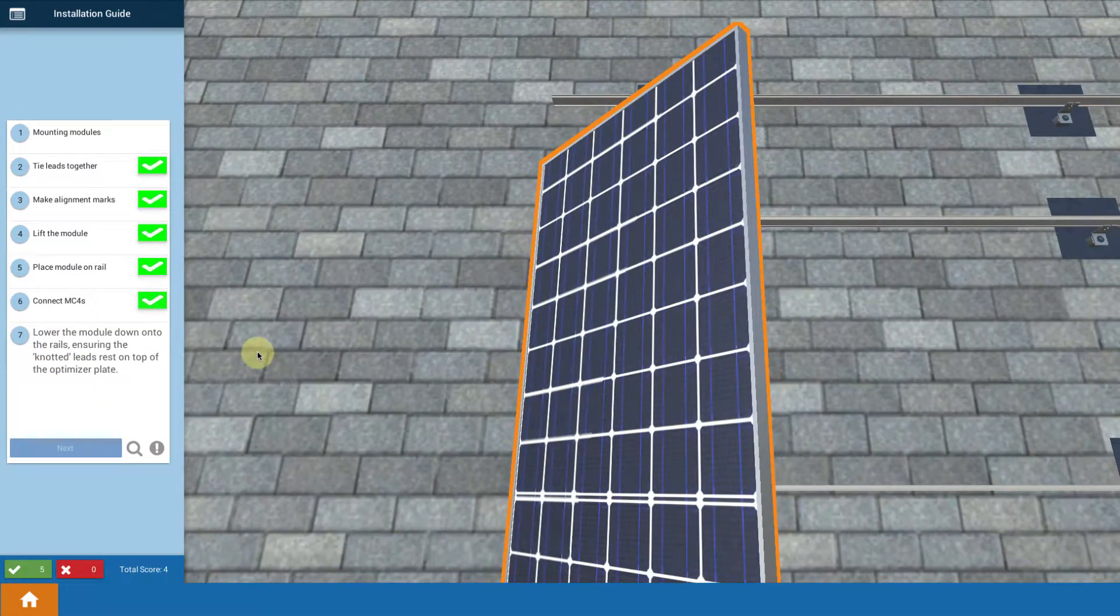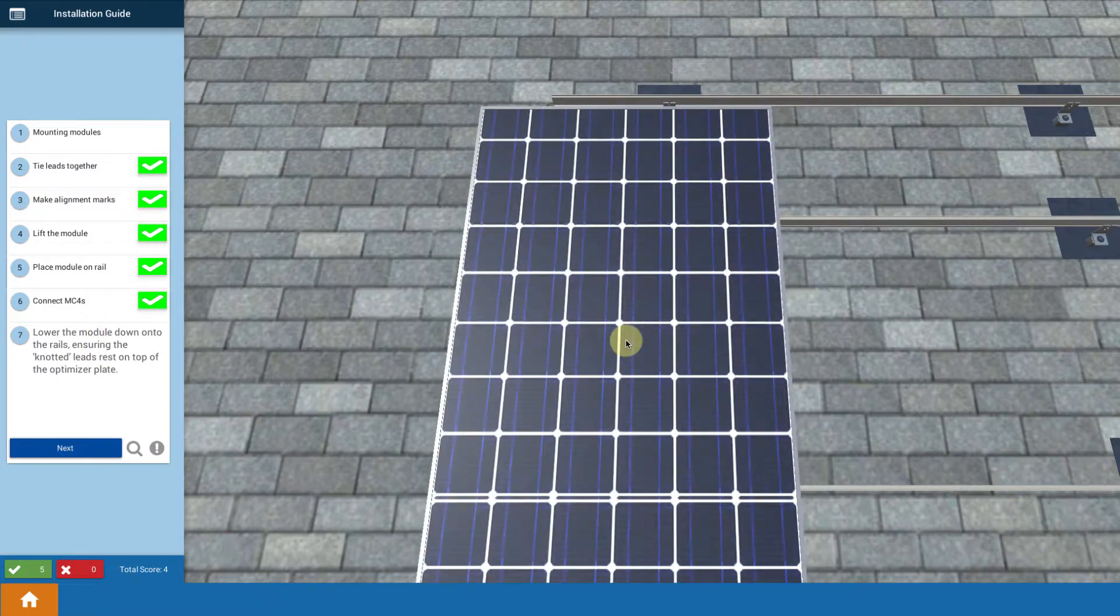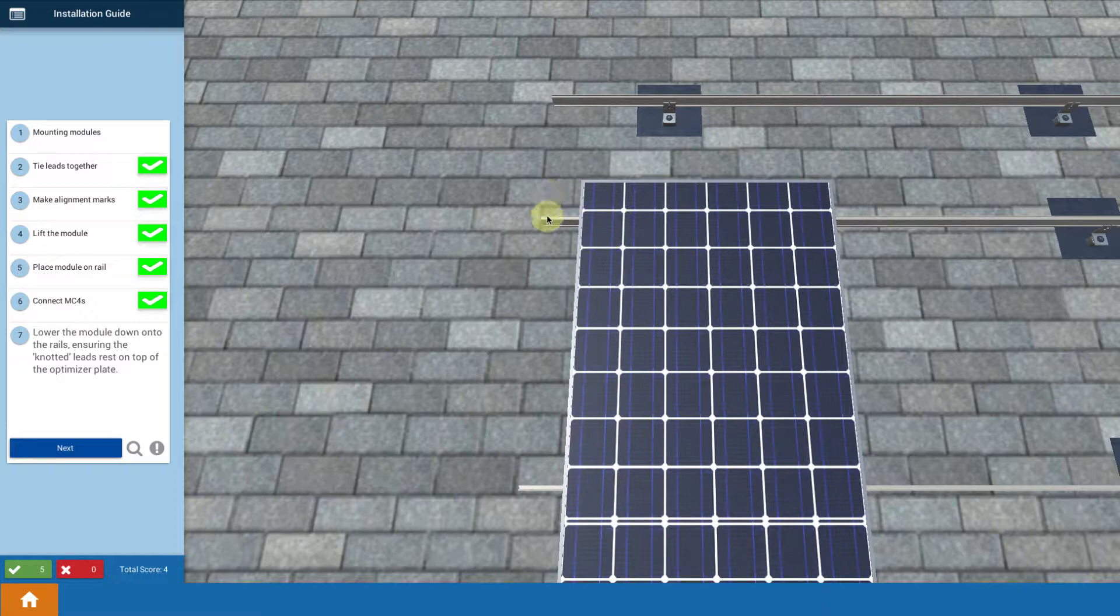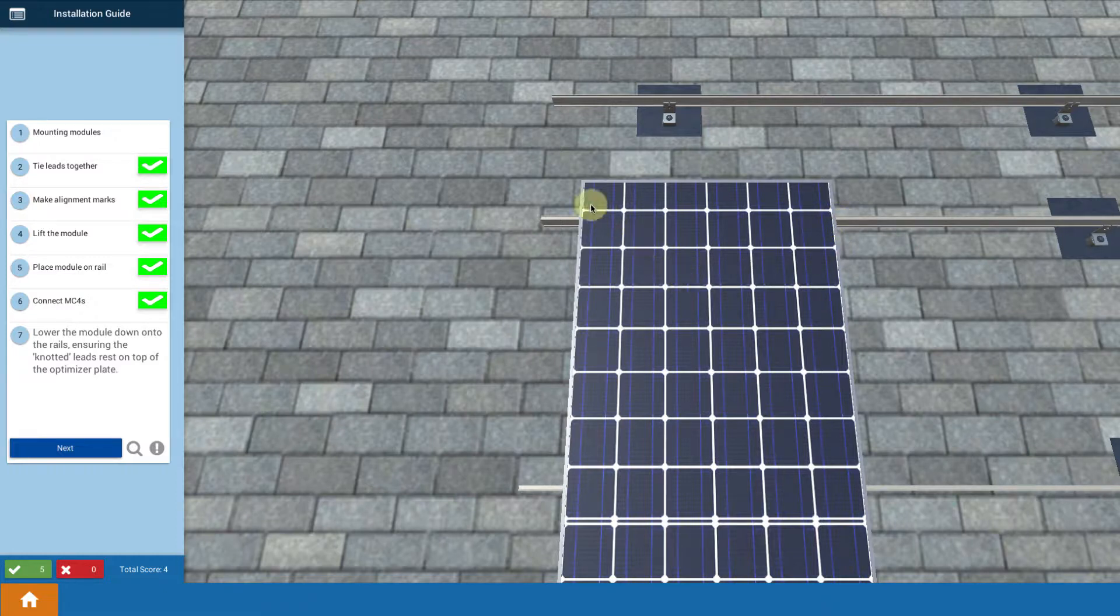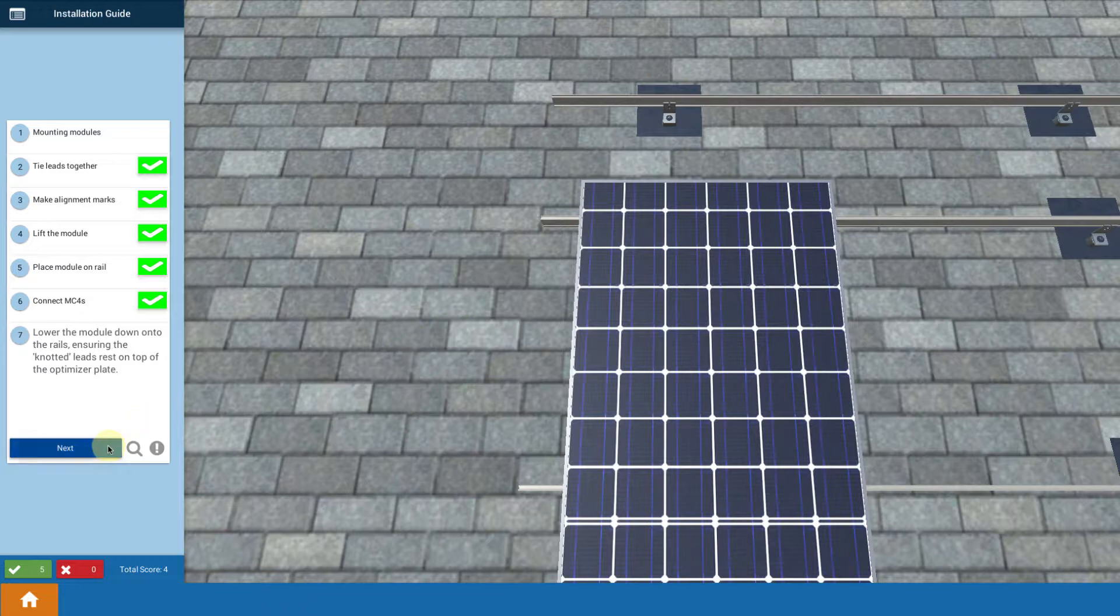Now this is a critical step. This is where we say lower the module down onto the rails. So you're going to touch on it and you're going to lower it down. But this is really important. This is where you want to watch out to make sure that you do not pinch your wires against your rails. So you've got a module with a metal frame and you've got a rail with a metal rail. You don't want those wires to in any way get pinched here. So that's a real important thing to check as you lay them down.